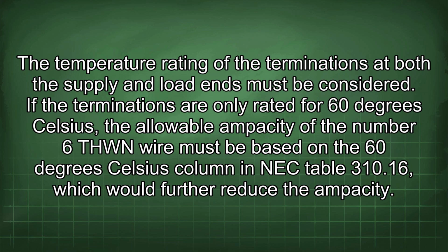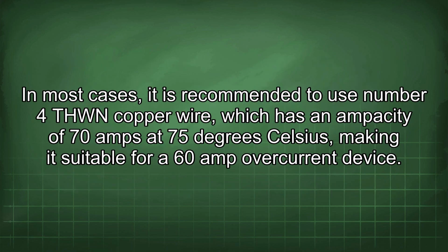If the terminations are only rated for 60 degrees Celsius, the allowable ampacity of the number 6 THWN must be based on the 60 degrees Celsius column in NEC Table 310.16, which would further reduce the ampacity. In most cases, it is recommended to use number 4 THWN copper wire, which has an ampacity of 70 amps at 75 degrees Celsius, making it suitable for a 60 amp overcurrent device.